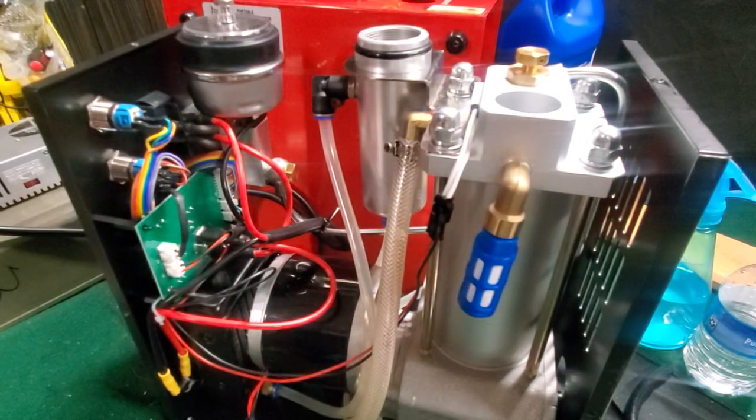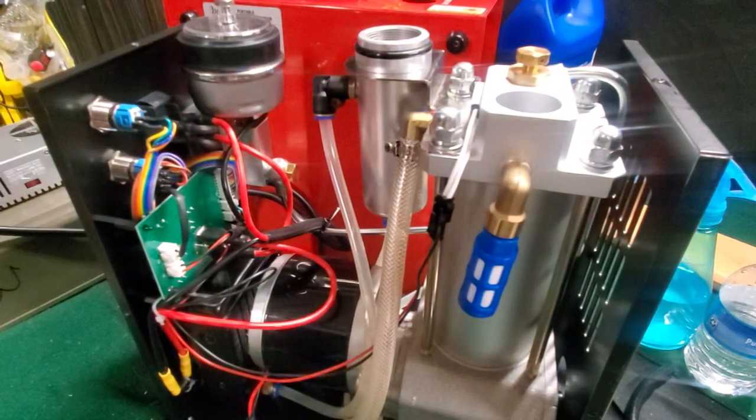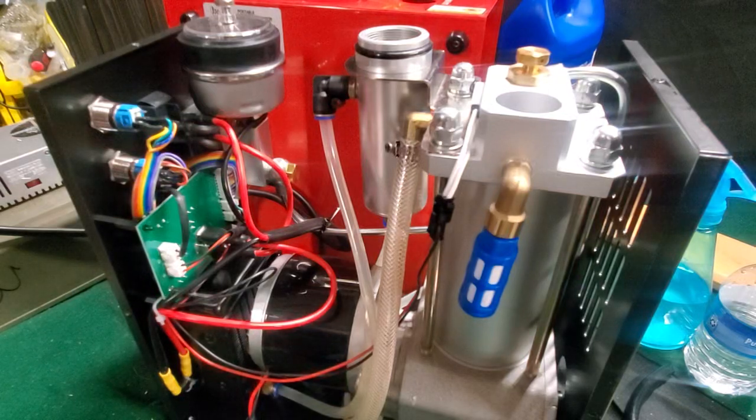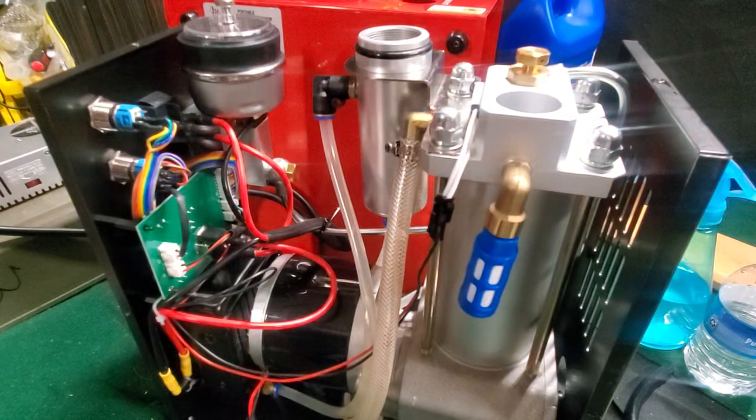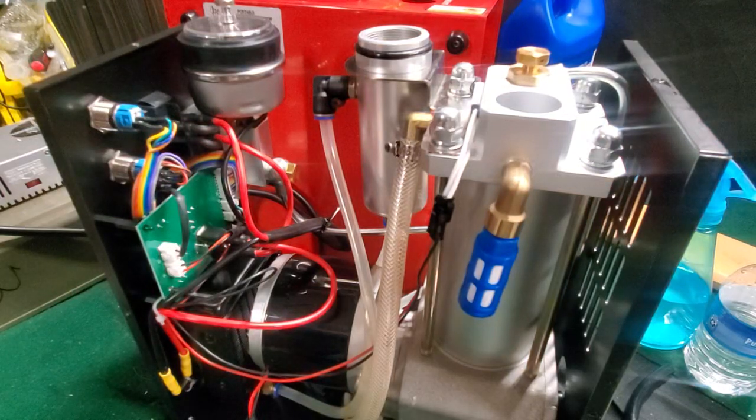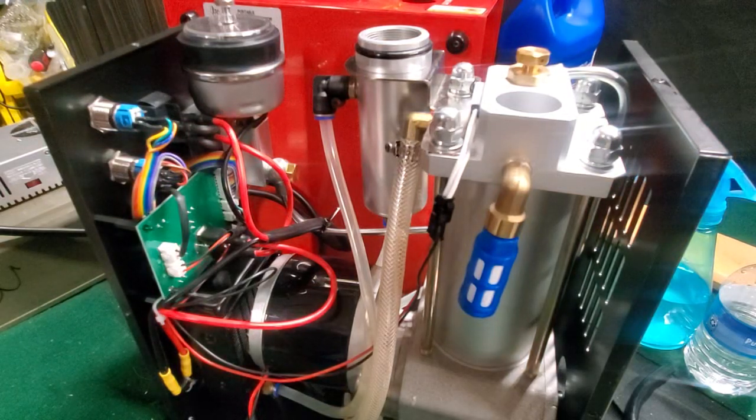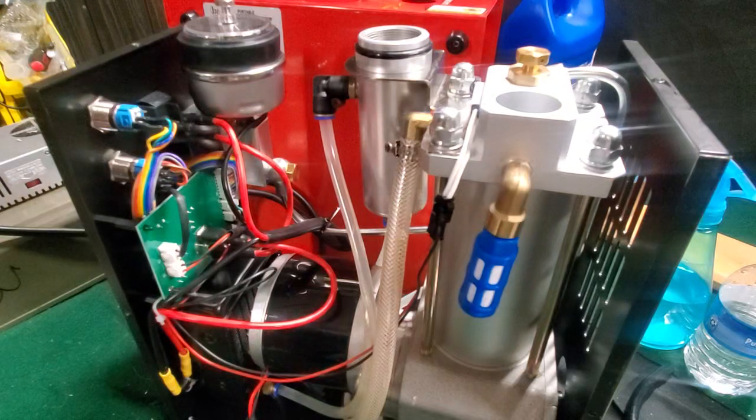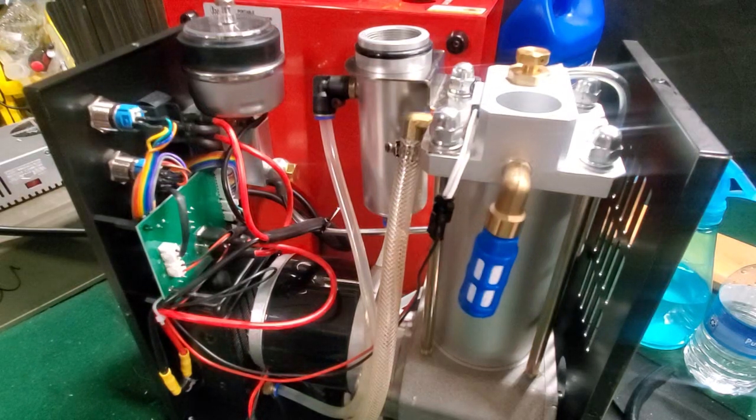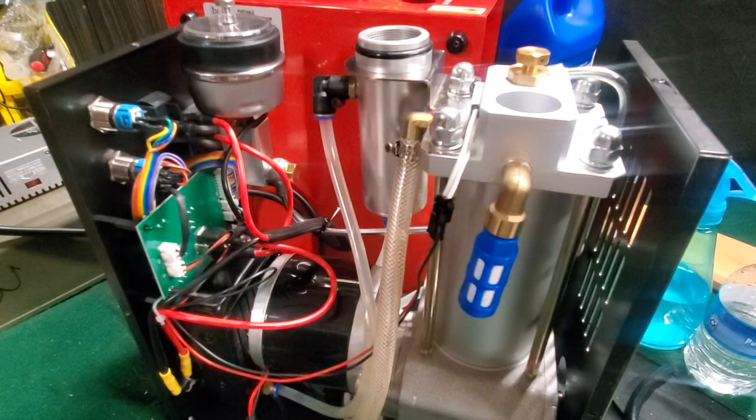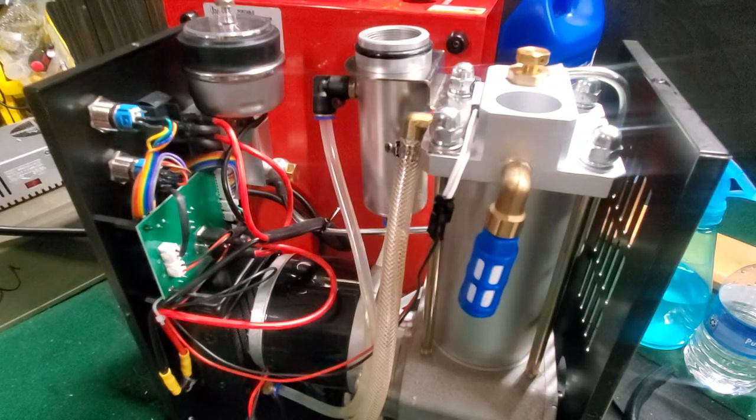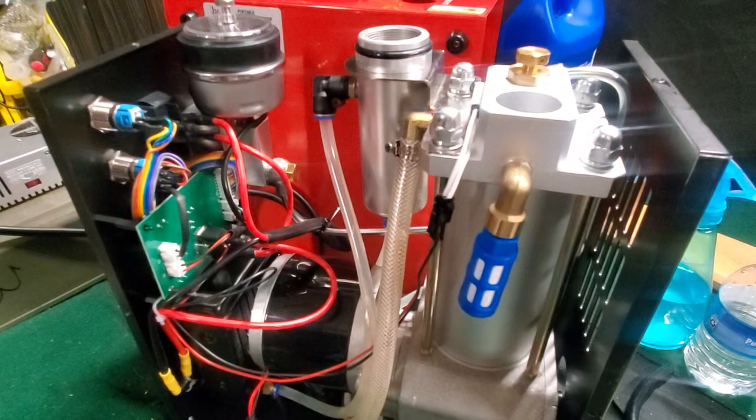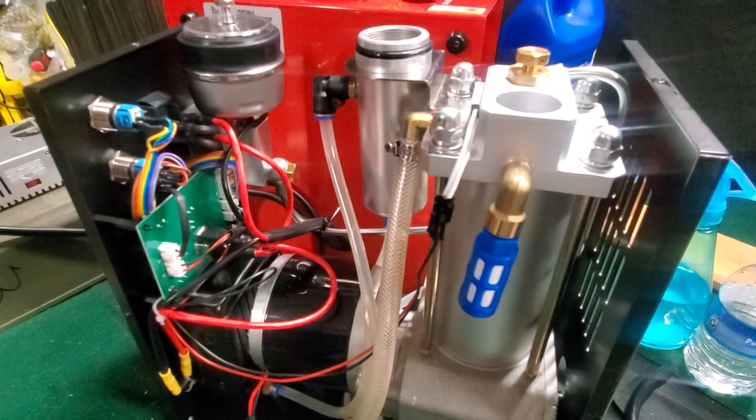Now I'm going to show you how to set up the CS4 for your initial fill with coolant. If you're in cold climates, make sure you use antifreeze, not just straight water, because you're going to freeze these compressors. I've come across a couple that have been frozen already. We don't want to do that.